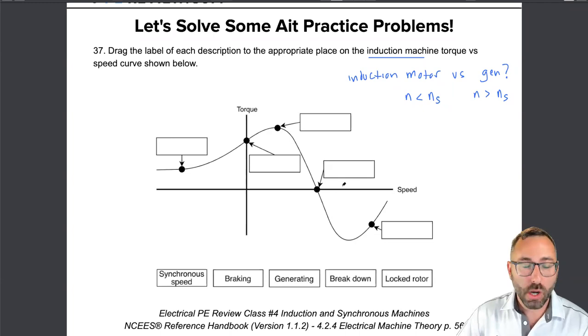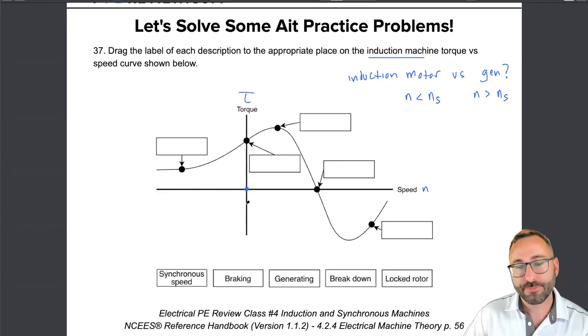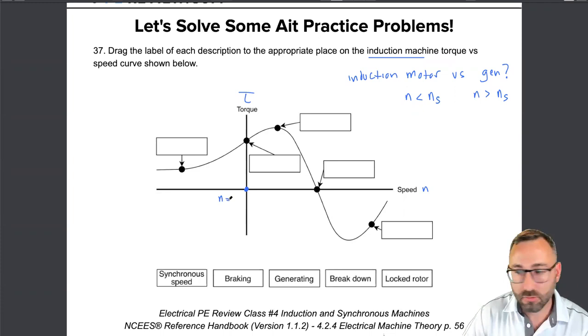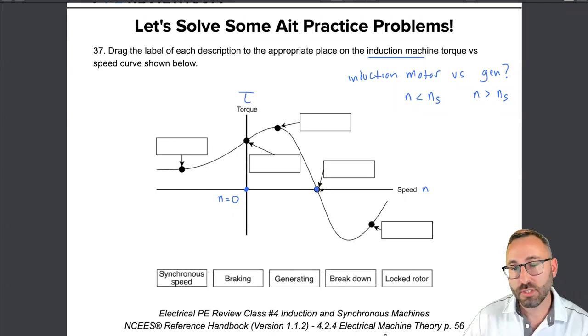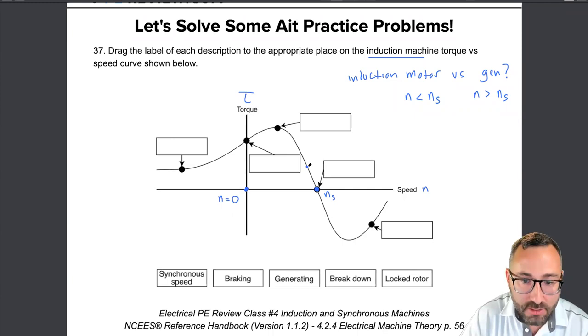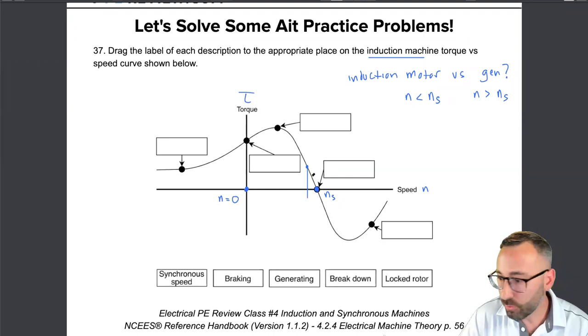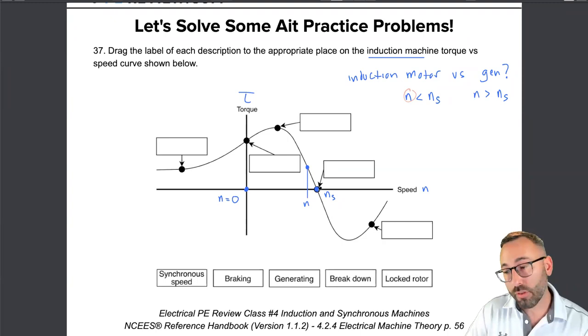For a generator, the rotor spins faster than synchronous speed — it pushes out power as a source instead of drawing power in as a load. On the torque versus speed curve, these curves vary depending on the motor type (NEMA design A, B, D, etc.), but the main points are the same. On the horizontal axis: N equals zero on the left, synchronous speed NS is our reference point, and full load speed N is slightly slower than synchronous speed for a motor.